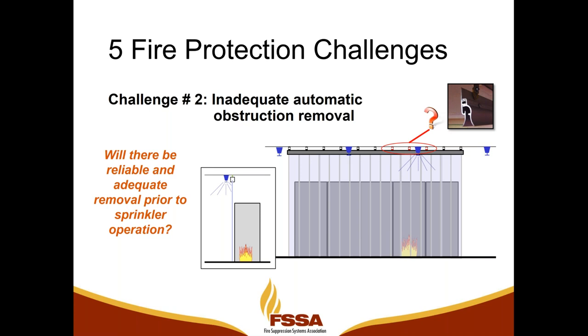In this picture, imagine a fire inside of or next to an aisle containment or a contained aisleway. All of those fusible links would have to receive enough heat for them to fall away. Imagine if the sprinklers were outside of that contained aisleway and the fire was inside. Think about how big that fire would have to be before all the fusible links melted and the first sprinkler was able to receive enough heat to operate. That's the major problem with the fusible link-based systems. In practical reality, they're not going to help improve the performance of the fire sprinklers, and they're really going to cause the fire to be larger than it needed to be in the data center and delay the sprinklers from operating and acting upon that fire to control its growth.